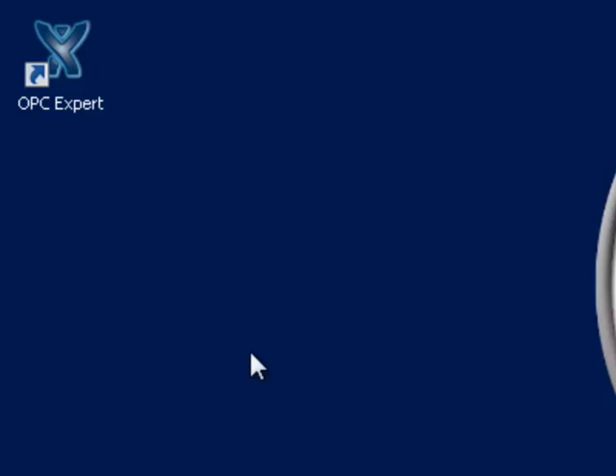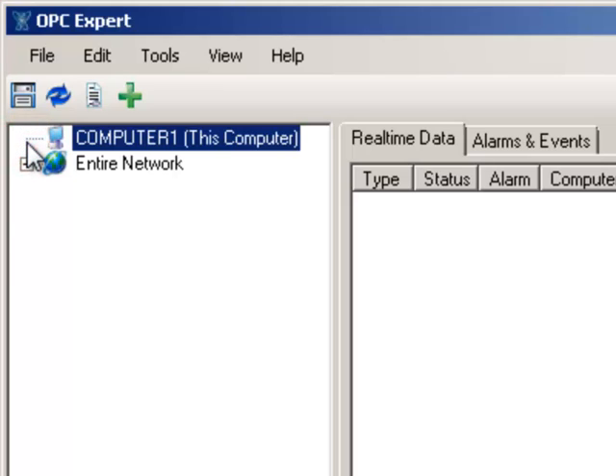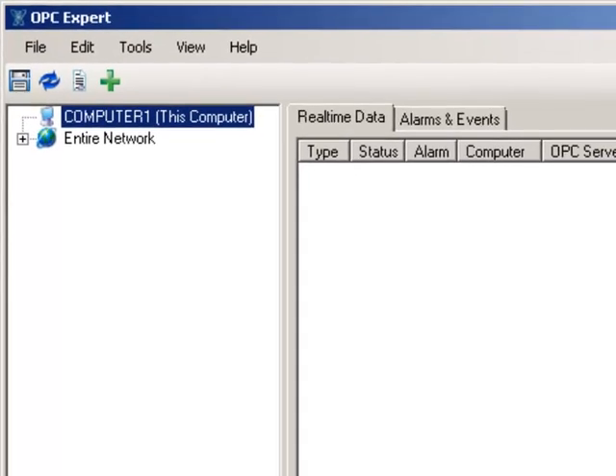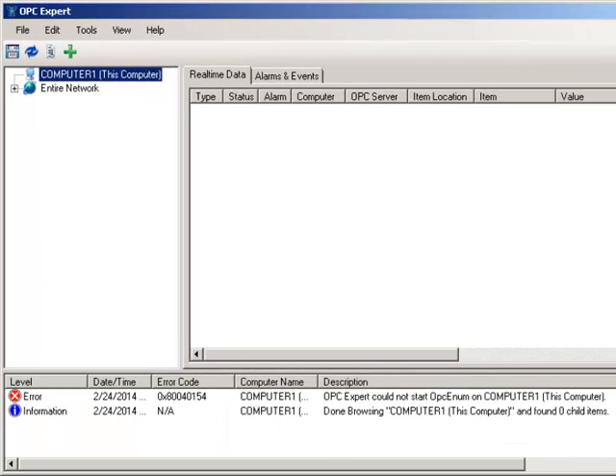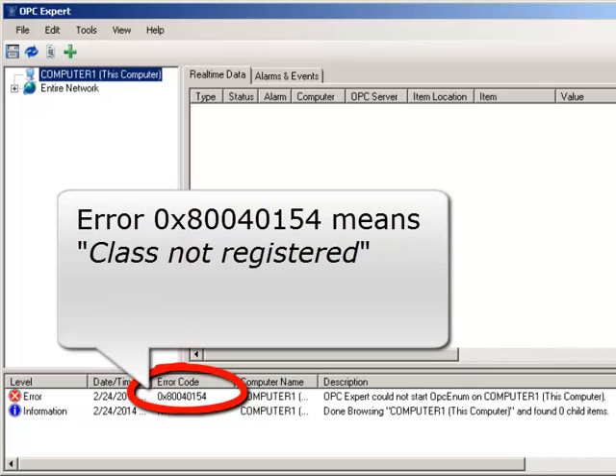Let's start OPC Expert and connect to an OPC server. Open this computer so we can browse for available OPC servers. Normally, we would expect the computer to open, but it did not. In the event window, we see OPC Expert already shows error 0x80040154. Windows describes this error as class not registered.